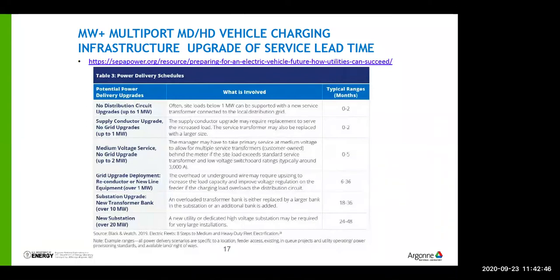For 5 months is what happens when I have to have medium voltage. So the first two are low voltage 480 volt 3-phase. The other is medium voltage, where you take in a primary service of 13.2 up to 138 kV. Then typical transformers are limited to 3,000 amps, and that's important to know. It's like when I need more than 2.5 or 2 megawatts, right, but I need 20. Well, you're only getting 2. Then what? Well, that's the next slide we're going to talk about.